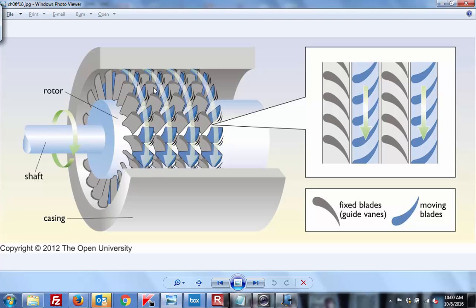The fixed vanes then say, hey, change course. I know you were happy moving that way, but here comes another round of vanes, so the stationary ones kick them back straight so that energy can then become rotational again. And with each step, the gas expands, so these get bigger and bigger as you move through the technology. And there's a lot of physics that goes into designing these things. Huge computational, numerical, dynamic simulations.